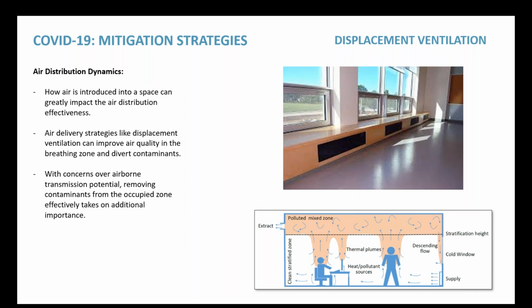With a displacement system, if you have a large open area that isn't full of partitions or cubicle walls, where you can get good airflow into the center of the space, the thermal plumes of the people or the computers in the space create a stratification that lifts the contaminants and pollutants up out of the breathing zone into what is referred to as the polluted mixing zone. And then once the contaminants are up there, you have high-level return and exhaust grilles that can remove those contaminants. So it helps keep contaminants out of the breathing zone.